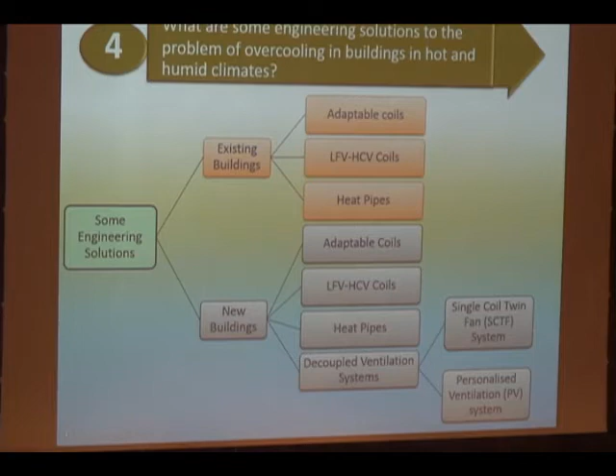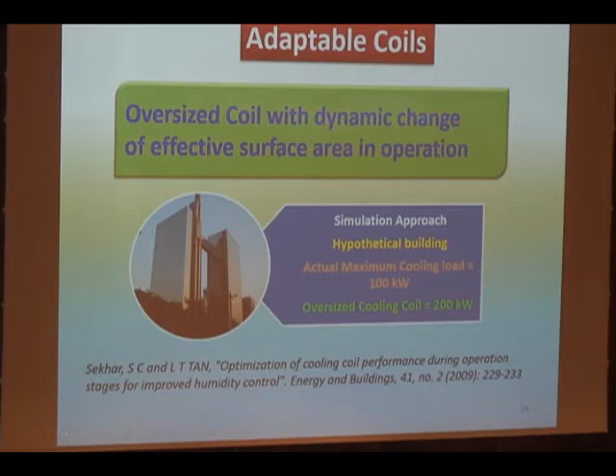If we can have a strategy, a technology approach, if you like, that allows us to change the coil or change the heat transfer surface area required in dynamic range, wouldn't that be a great idea? So let's just see what happens here. This was a simulation study that we did a few years back. So here, what you can see is an oversized coil with 200 kilowatts cooling load, because that's what a consultant would typically do. He would never underestimate the cooling requirements, because as a consultant, you're responsible for capacity provision in the building design.